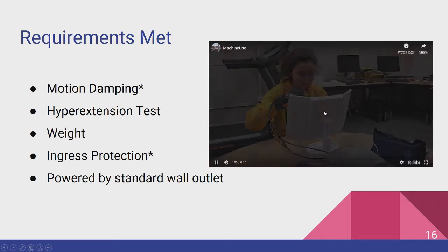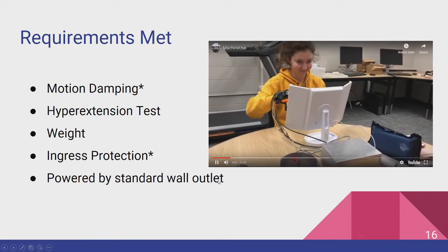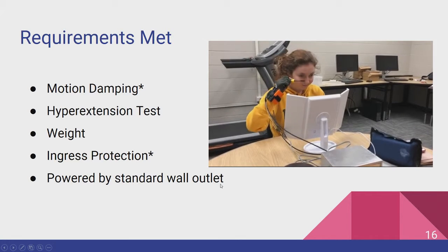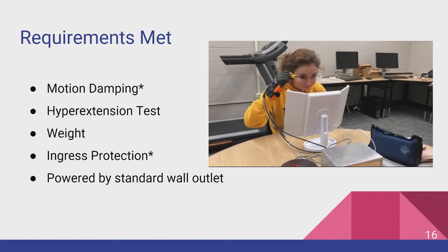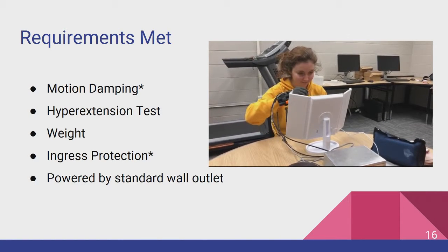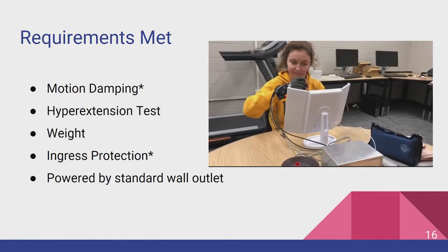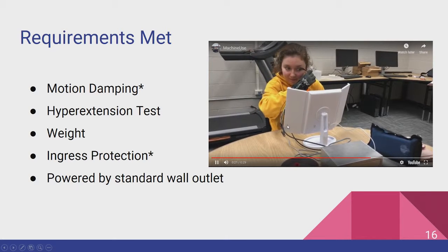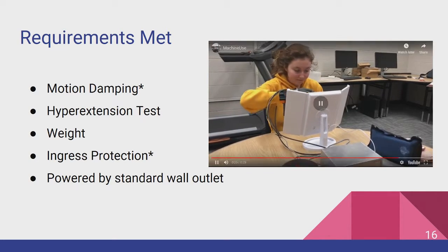Moving on to the testing portion of our presentation. The requirements that the team did meet: for the motion dampening test that we did, one of our motors was down during the time of testing. However, despite the motor being down, we still had one going, and so it was able to dampen the tremors within our required range of 4 meters a second squared to 0.5 meters a second squared. With the one motor being down, we just weren't able to enter into the compensation mode, which allowed for intentional movement. However, even though the device stayed in the first phase, it was still able to meet our motion dampening requirement. For the hyperextension test, the maximum angle that the device pulled the wrist to was 20 degrees, and the requirement was 40 degrees, so that was within our limit.